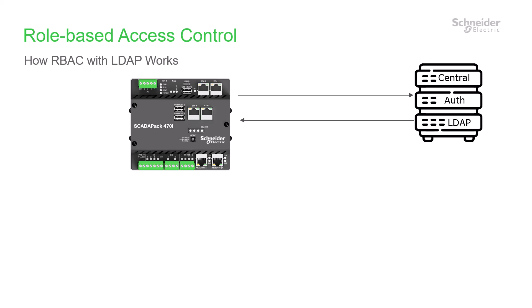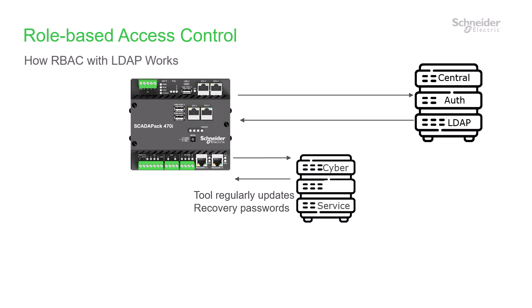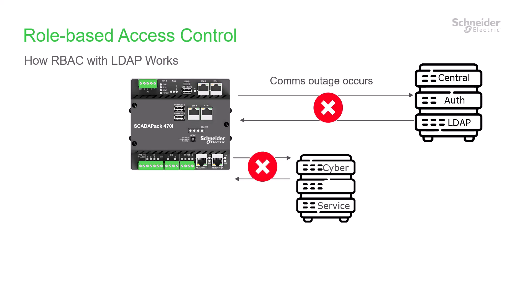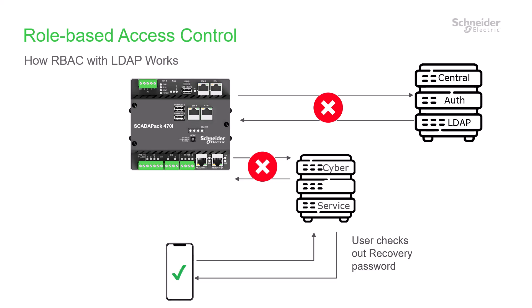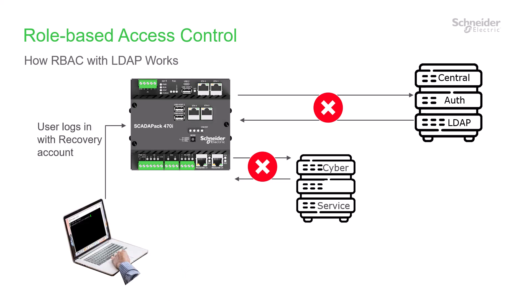If the server has your account in its database, it responds to the SCADAPack with a message authenticating and enabling access to the RTU functions authorized for your specific roles. You can configure an RBAC-enabled SCADAPack to use both an Active Directory server and local user accounts. A cyber service tool can regularly update the local user passwords. If communication to the management server is lost, you can check out a local password from that tool.